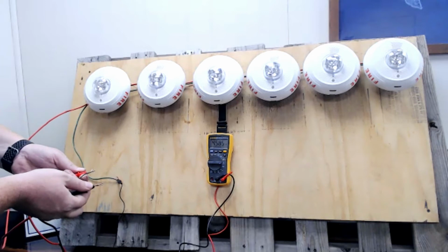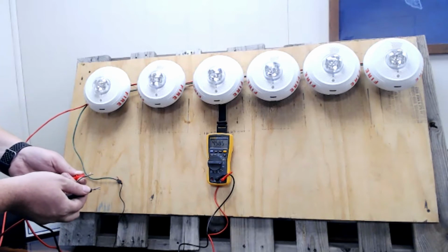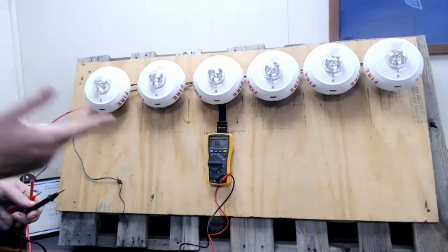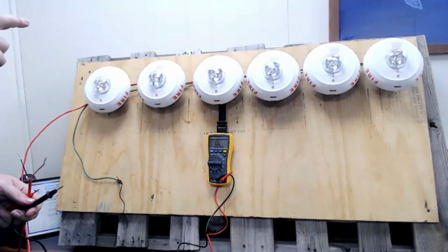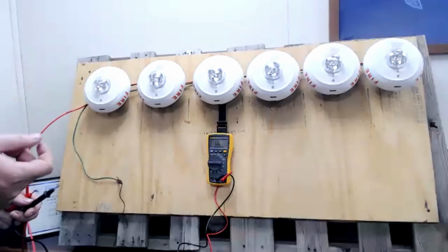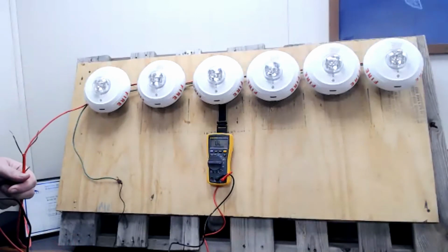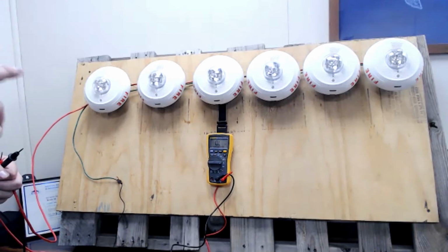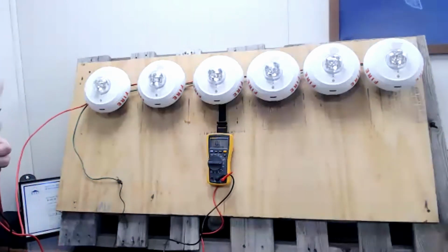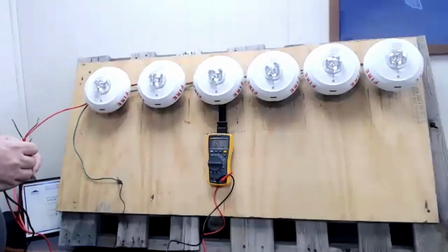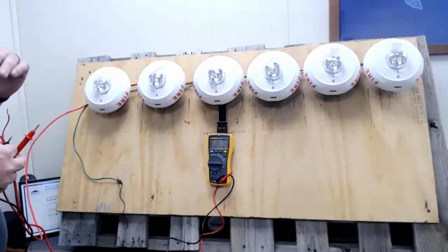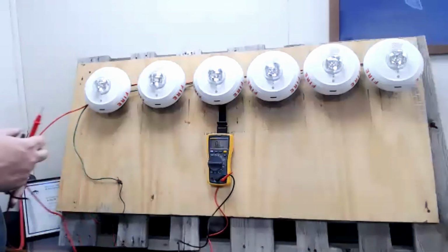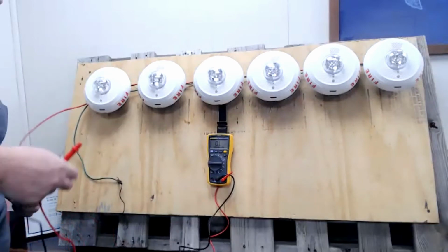4.5 K ohms. Okay, maybe I didn't put a reverse device in here like I thought I did, because that's what we want to see. We want to see that there is a difference. If I check it both ways and see like 4.5 K ohms or 4.2 K ohms, that means there's a reverse polarity device, because you have that diode in there that reads different one way than the other. But if they're all facing the same way, they're going to read the same. So I don't have to chase a reverse polarity device. Threw myself off there. Thought I put one in.